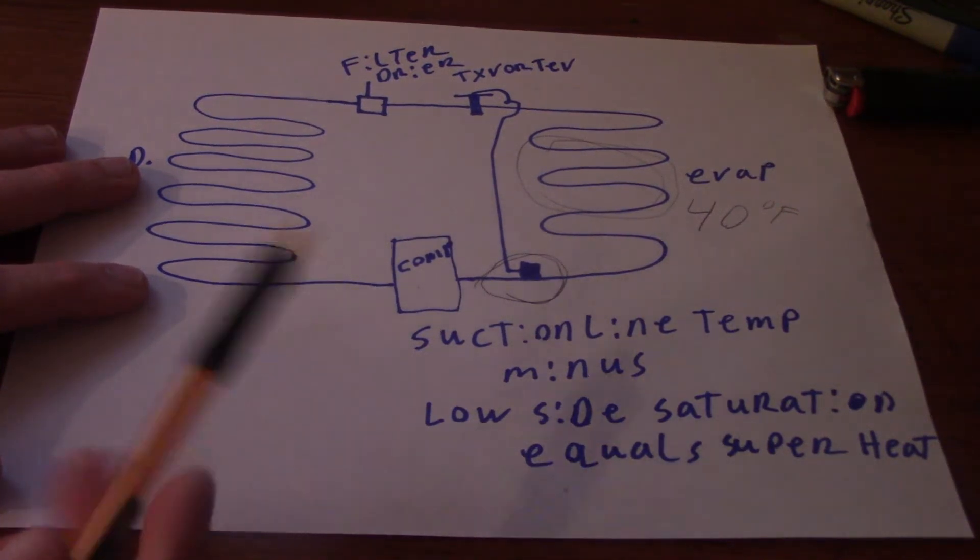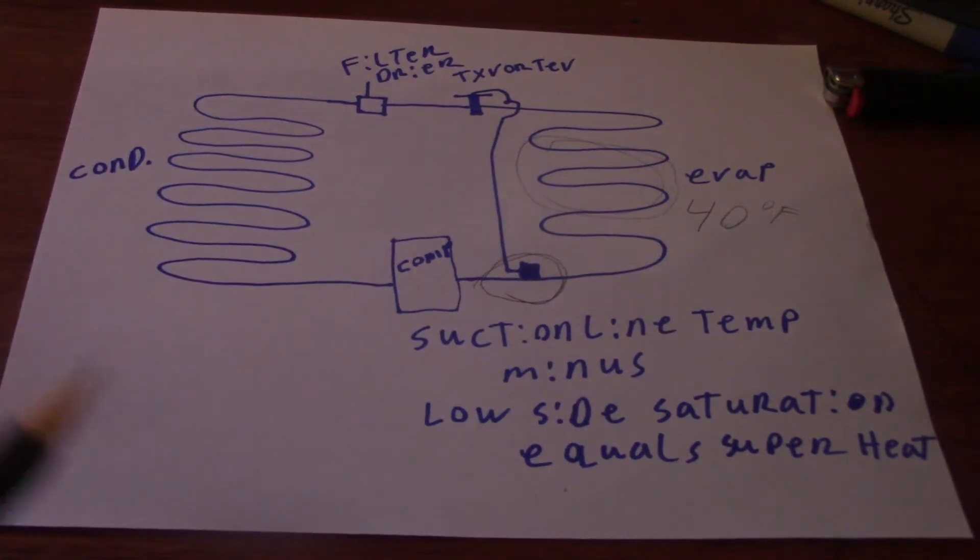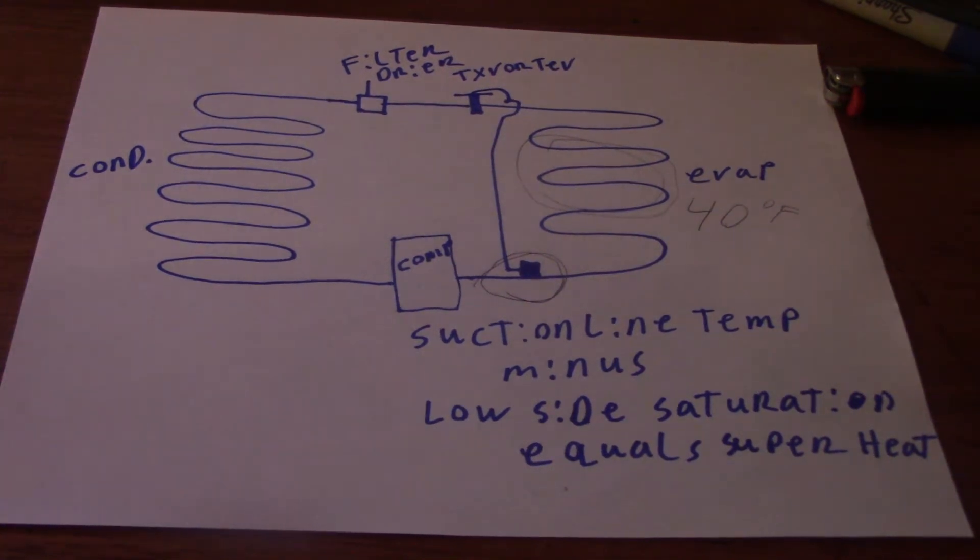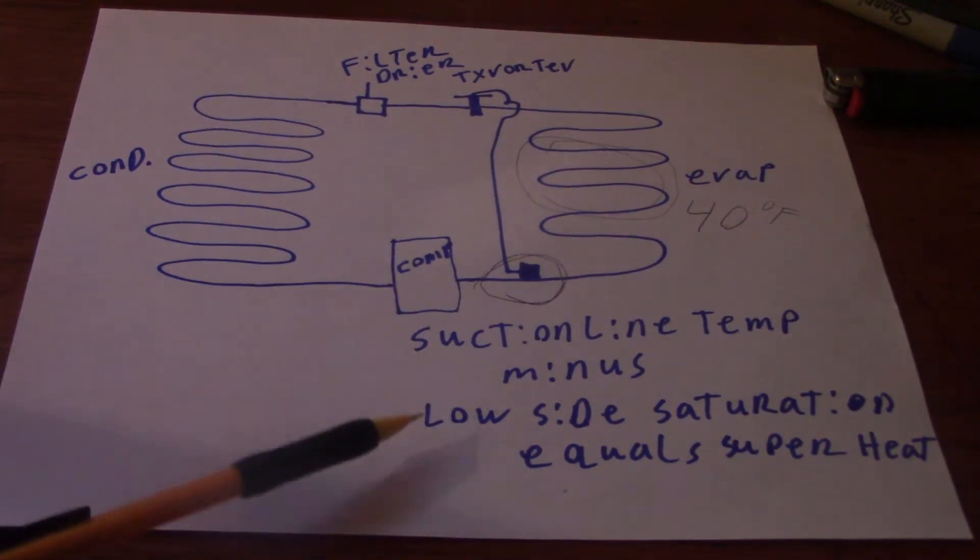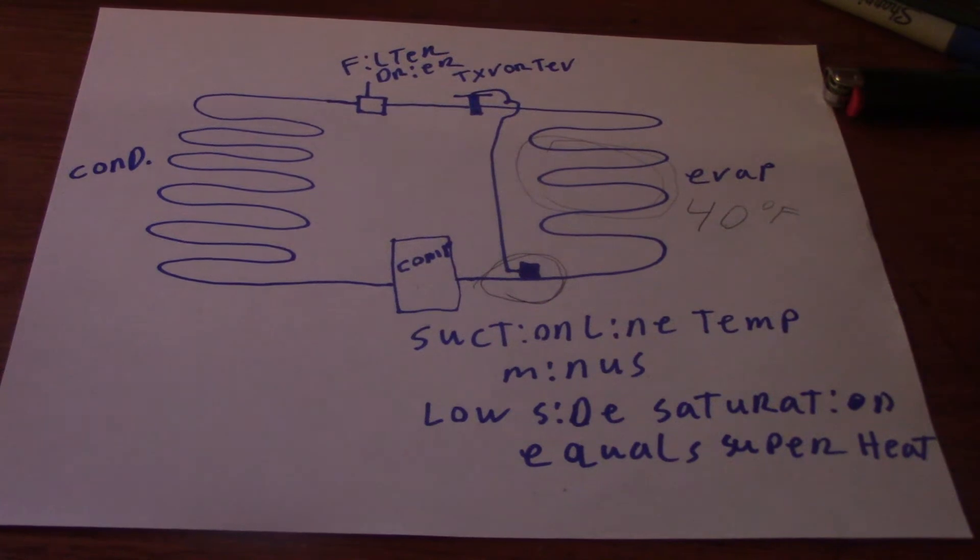All you're doing essentially when you calculate superheat is check the level of refrigerant in the system, if it's a cap tube or piston, or the TXV, verified TXV operation. It's important that you get the calculation right by doing a suction line minus low side saturation, as that's the formula. If you get it backwards, you can come up with a wrong number and you have no idea if the system's broke because you did the math wrong.